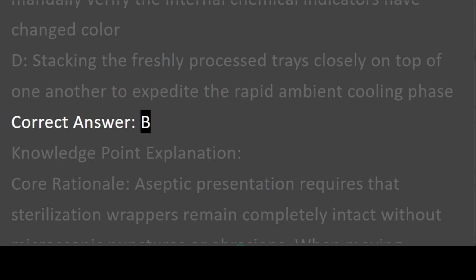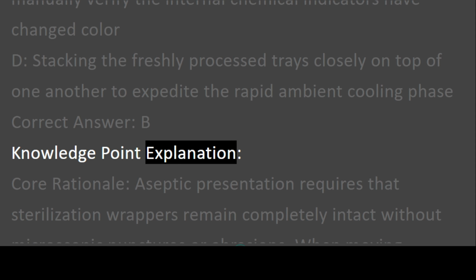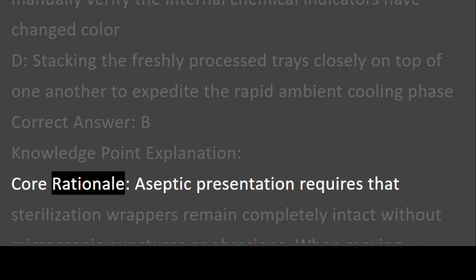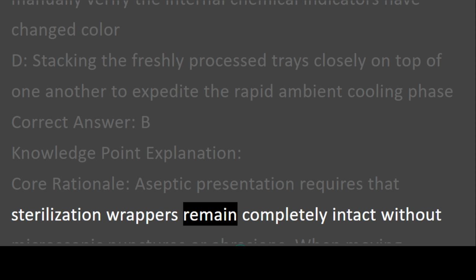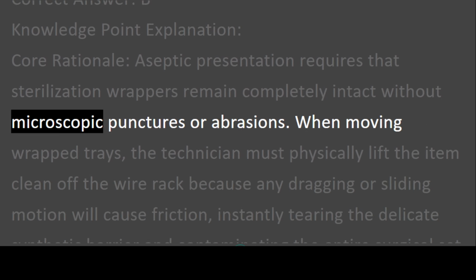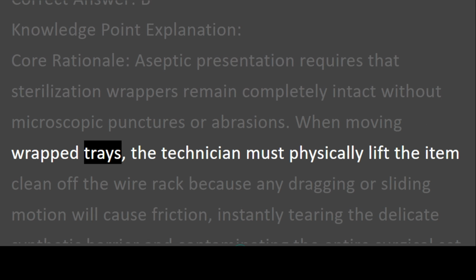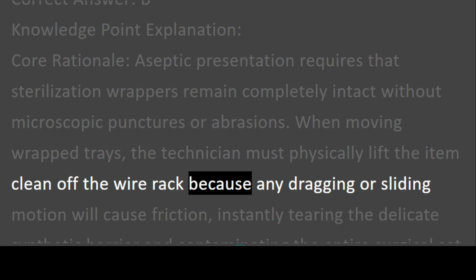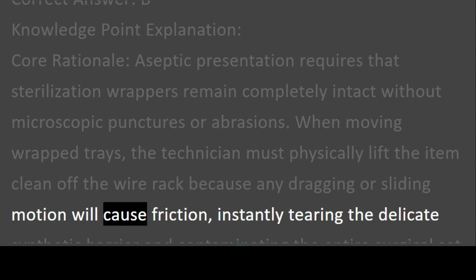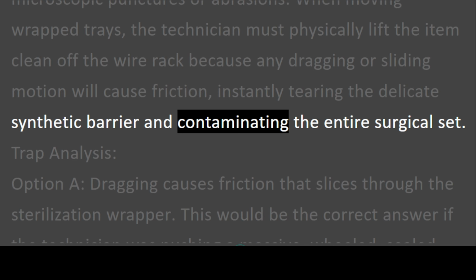Correct answer, B. Knowledge point explanation. Core rationale. Aseptic presentation requires that sterilization wrappers remain completely intact without microscopic punctures or abrasions. When moving wrapped trays, the technician must physically lift the item clean off the wire rack because any dragging or sliding motion will cause friction, instantly tearing the delicate synthetic barrier and contaminating the entire surgical set.